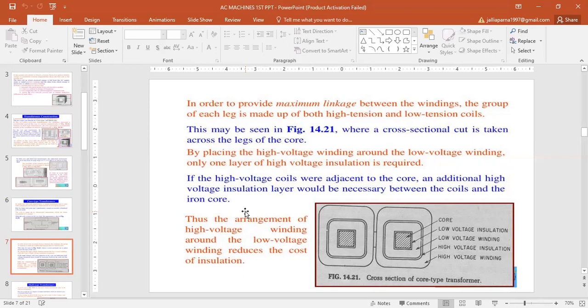By placing the high voltage winding around the low voltage winding, only one layer of high voltage insulation is required. If the high voltage coils were adjacent to the core, an additional high voltage insulation layer would be necessary between the coils and the iron core. Thus, the arrangement of high voltage winding around the low voltage winding reduces the cost of insulation.